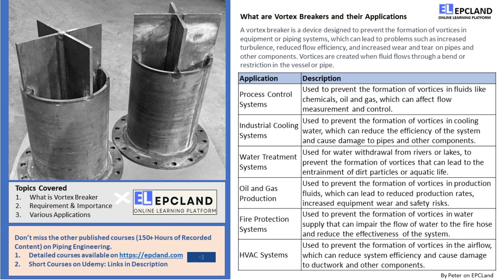A vortex breaker is a device commonly used in industrial and commercial applications to prevent the formation of vortices in equipment or piping systems. Vortices can cause problems such as reduced flow efficiency, increased turbulence, and wear and tear on components. Vortex breakers are typically small, cylindrical, triangular, or cross-shaped devices installed in a pipe or vessel where a vortex is likely to form. They create a disturbance in the fluid flow that breaks up the vortex before it can form, thus preventing the problems caused by vortices.